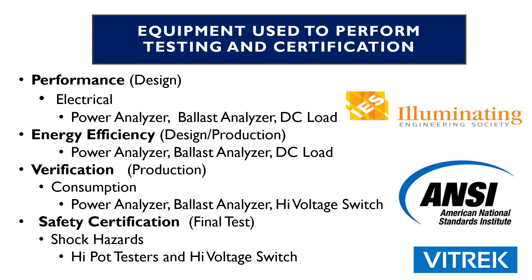Energy efficiency testing can be done with a power analyzer, ballast analyzer, and DC load. On the verification side, from a consumption standpoint, again a power analyzer, ballast analyzer, and a high-voltage switch — which is a special product in the Vitrek product line that we'll go over in a bit more detail. From safety certification, which is typically on the final test side, for shock hazards you'll use a hipot tester and possibly a high-voltage switch, depending how many products you want to test at a specific point in time.